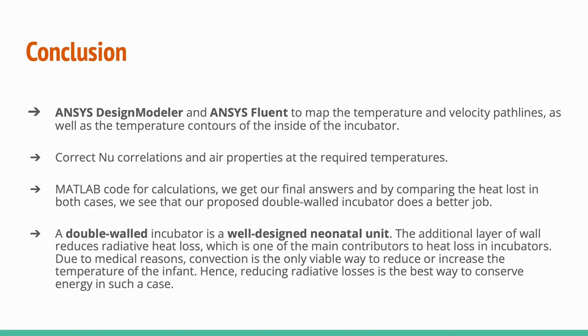The double-walled incubator is a well-designed neonatal unit. The additional layer of wall reduces radiative heat loss, which is one of the main contributors to heat loss in incubators. Due to medical reasons, convection is the only viable way to reduce or increase the temperature of an infant. Hence, reducing radiative losses is the best way to conserve energy in such a case, and this is achieved by the double wall design.